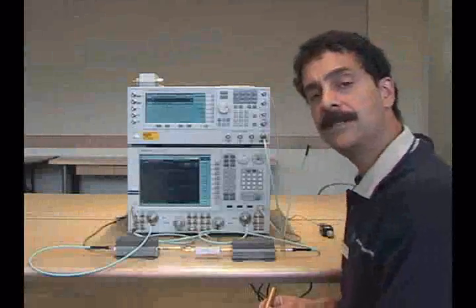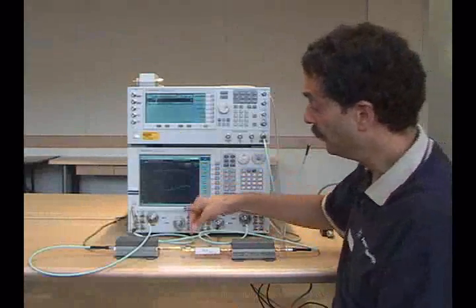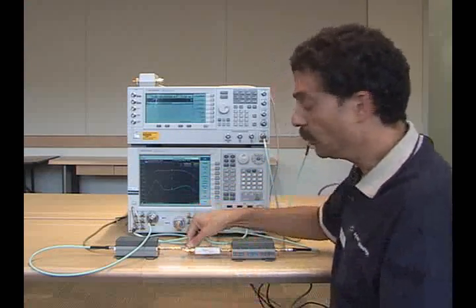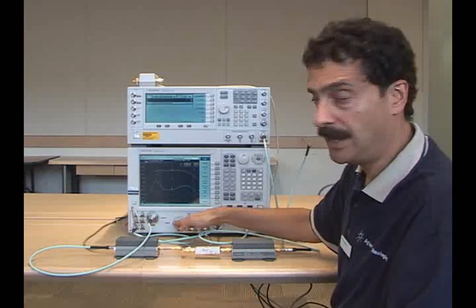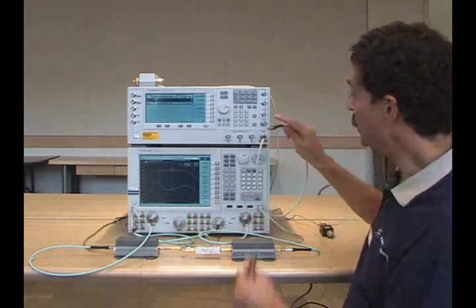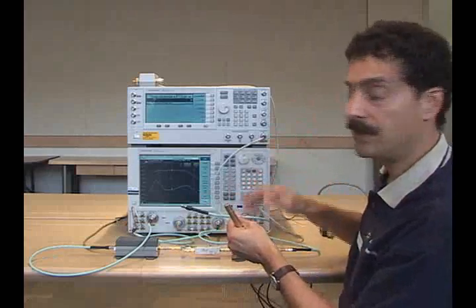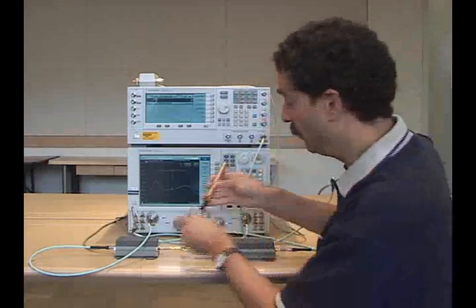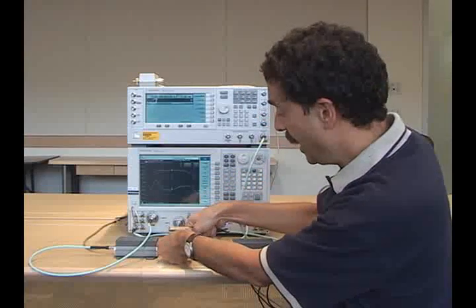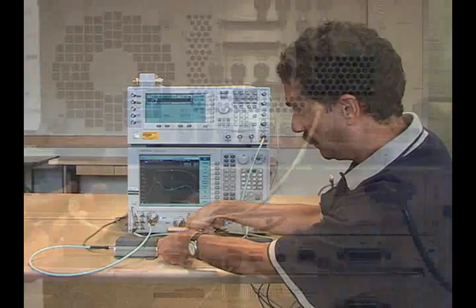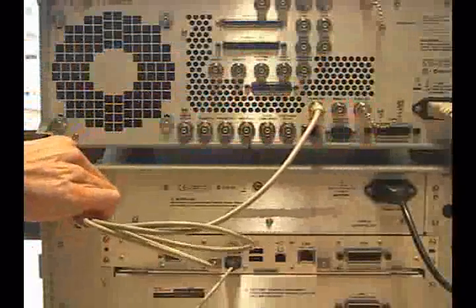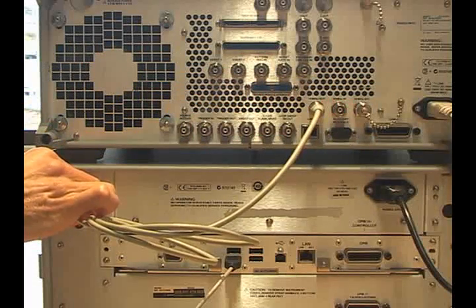In this next step of the demo, I'm going to remove the local oscillator signal that's driving the mixer that's being supplied by the PNAX. And I'm going to substitute a local oscillator signal from our PSG signal generator. And we'll see the effect that that has on the measurement. So in this step of the demo, the time bases between the two instruments are locked together. So the 10 MHz out of the PSG is going into the 10 MHz reference in of the PNAX.